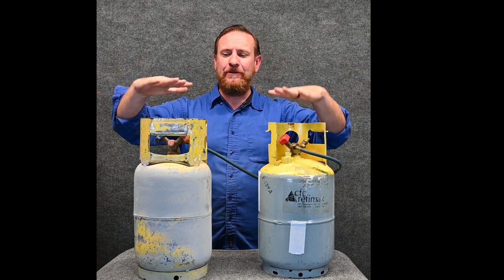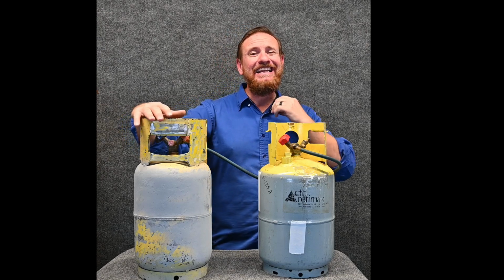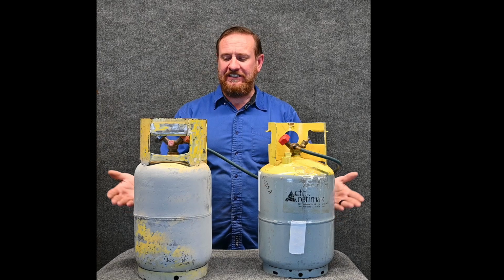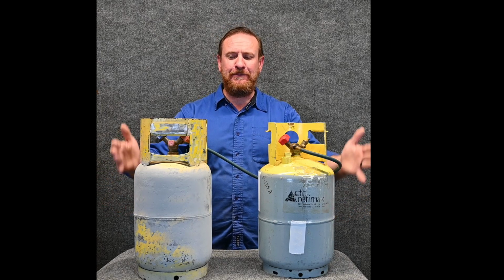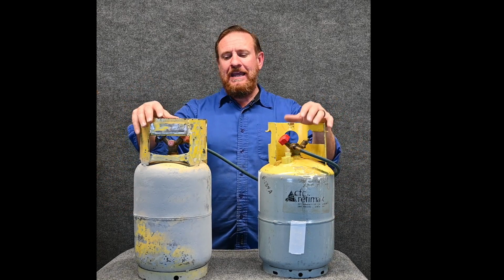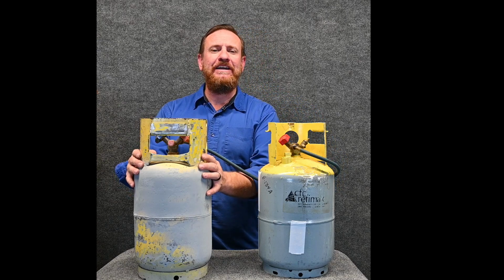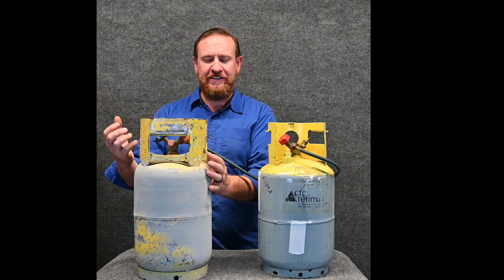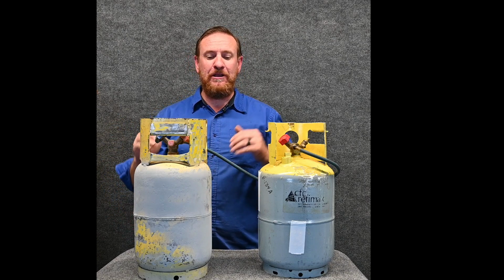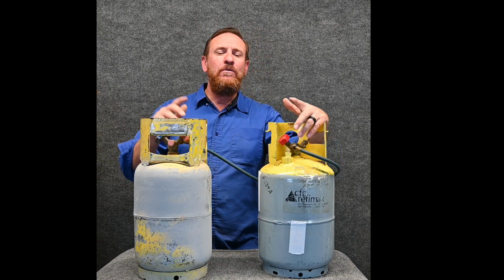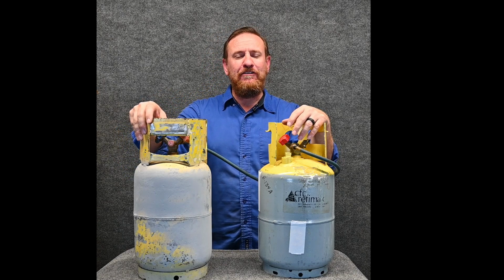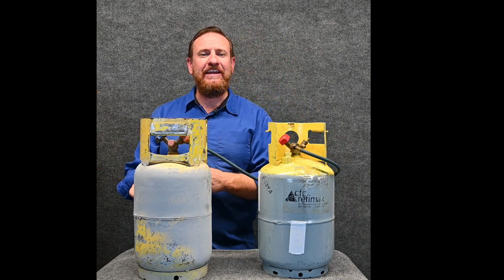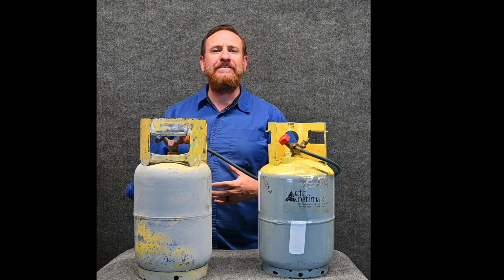Let's start over. Let's say they're both at the exact same temperature, 95 degrees, and we have liquid and vapor in both these things. Let's start over with 50% liquid, 50% vapor. Both tanks are in the same room temperature. And I was to take and put this one into a bucket of ice water. So the temperature of this tank drops, the pressure is also going to drop. But we have them connected with the hose. We're going to end up with refrigerant migration. The refrigerant from this tank is going to start migrating over to this tank. Refrigerant likes to migrate to the place that it's cooler.